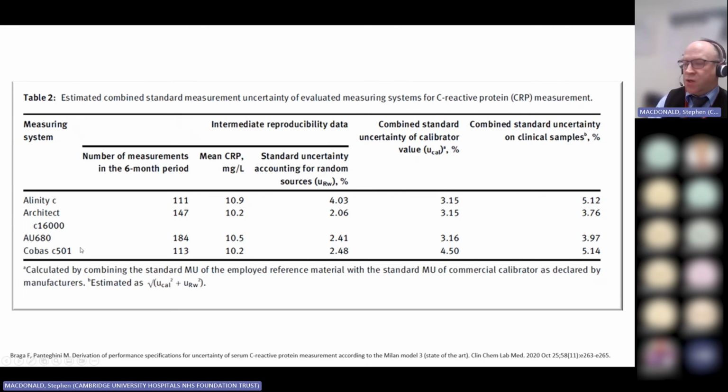But we can see across these four different methods, there is a difference in what the within-laboratory performance is. So this is just how the quality control is performing across the different methods, nearly a twofold difference across. In addition, the combined uncertainty of the calibrator value is slightly different, and this is despite them all using the same traceable reference plasma for each of the different methods.